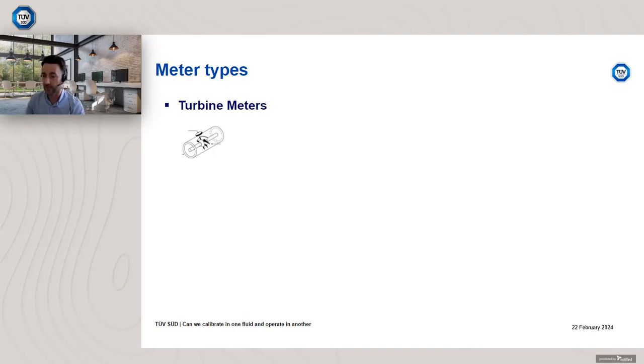Not all meters are suitable to be calibrated in a completely different fluid medium, and turbine meters are certainly one such device. PD meters are also similar. Again, if you have a gas PD meter, you can't calibrate it in liquid, and vice versa for both of them. So it's certainly challenging. PD meters in particular are viscosity sensitive devices, so you really do want to match fluid viscosity.